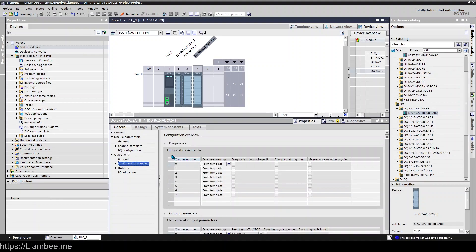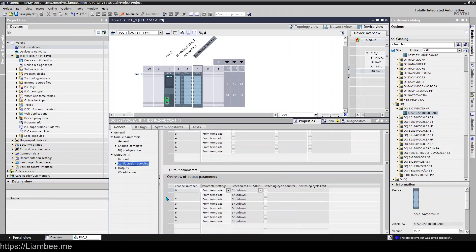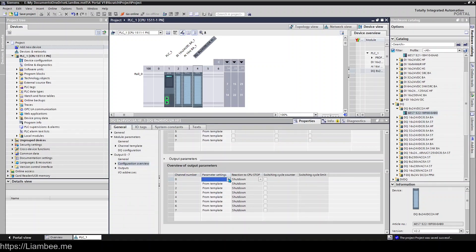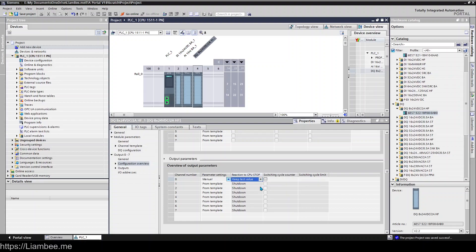You've got your diagnostics overview and then you've got your overview of output parameters, which is the same as what we looked at earlier. But instead of from the template, again you can do the same thing and say just channel zero, we want to set it to manual and we want this one actually to keep its last known value, even in the event of the CPU going off or shutting down.